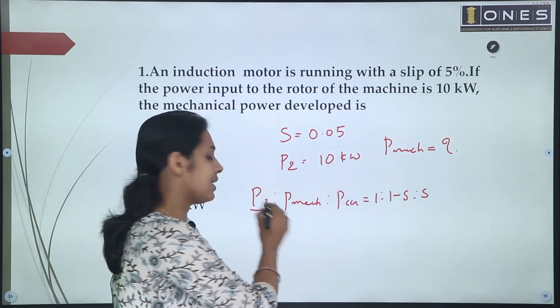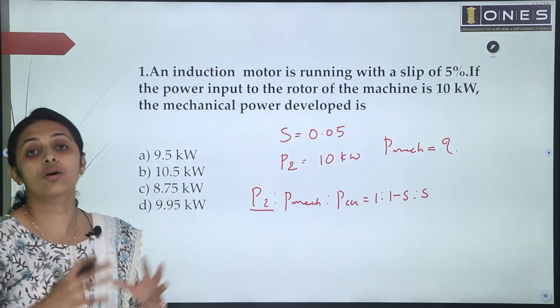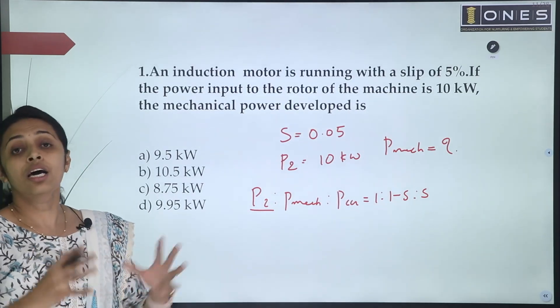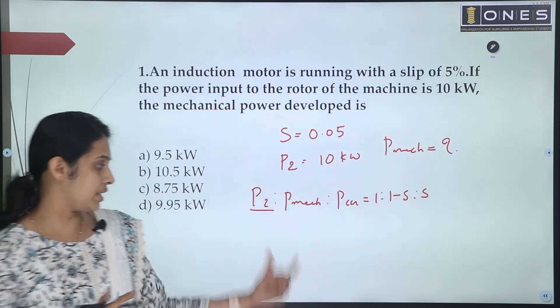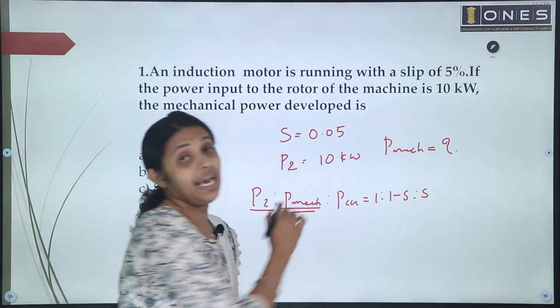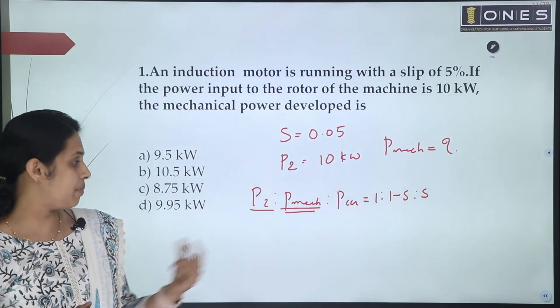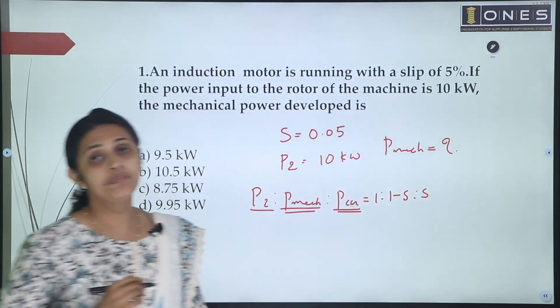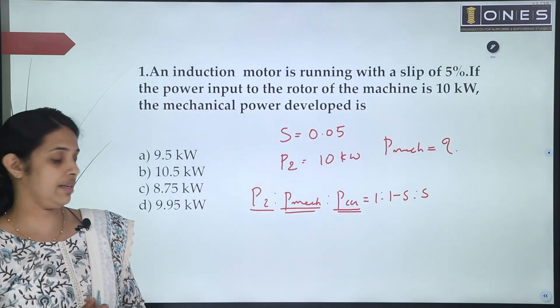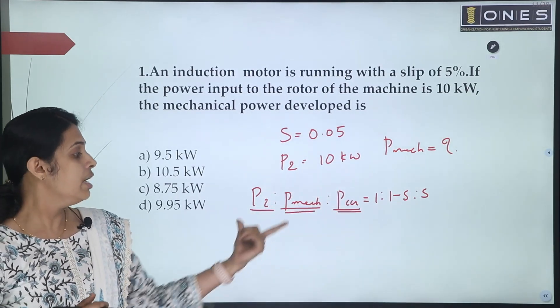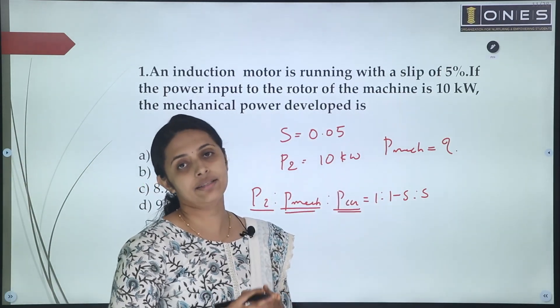P2 is the rotor input. Pmec is the mechanical power developed in the rotor. Pc is the rotor copper loss. So the relation is: P2 : Pmec : Pc = 1 : (1 - S) : S.